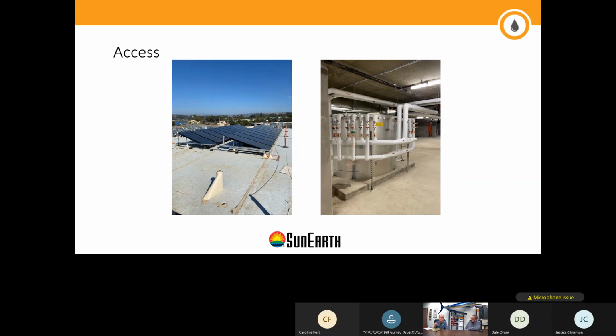Access is also a concern for electrical panels — people forget they need 3 feet of clearance. That's not always caught in plan check, because plan check may not show the electrical service panel. So access has to be maintained, especially in the mechanical room — you don't want to block any electrical access per code, as the National Electric Code spells out clearly.